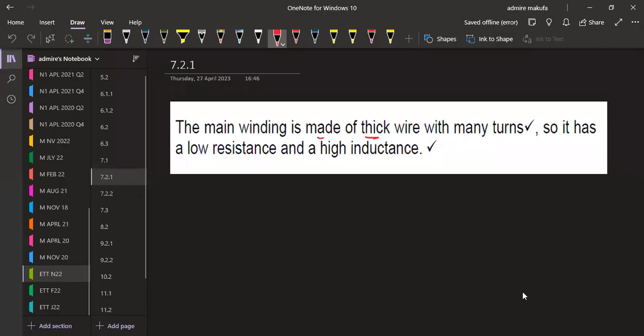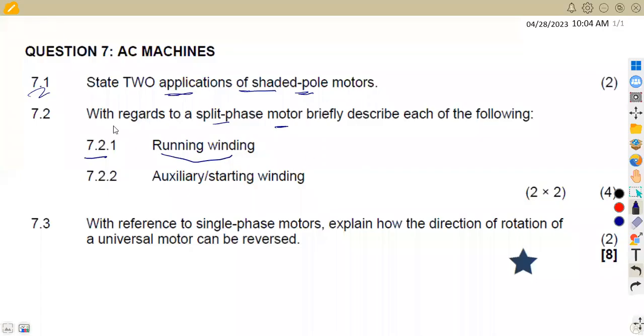...is made of thick wire with many turns. It has low resistance and high inductance. Take note: resistance is low, inductance is high for the running winding.